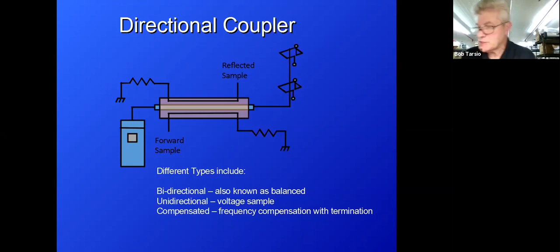So that's another aspect of this. But anyway, I wanted to talk a little bit about the directional coupler itself. There are principally 3 different types: bidirectional, also known as a balanced coupler, and a lot of the couplers that we use are bidirectional types. What you're looking at schematically here is that you have basically a pickup loop inside, and it has a termination on both ports. So let's say the forward side here, we actually don't use 2 halves of a coupler like this to do forward and reflected. We do it with the same port. We feed the forward port sample to the forward port input on our meter, and then the reflected port goes to the reflected port sample, and they're both 50 ohms termination, so inherently they're balanced and isolated. So that's the first style.